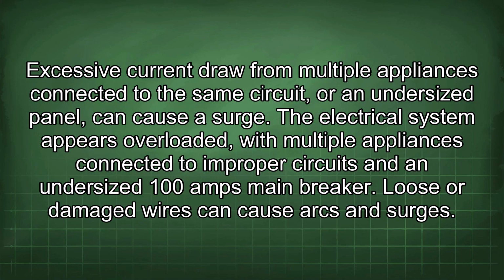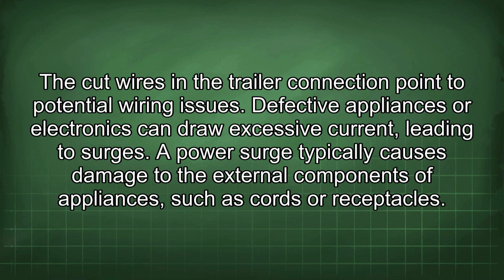Excessive current draw from multiple appliances connected to the same circuit or an undersized panel can cause a surge. The electrical system appears overloaded, with multiple appliances connected to improper circuits and an undersized 100 amps main breaker. Loose or damaged wires can cause arcs and surges. The cut wires in the trailer connection point to potential wiring issues.